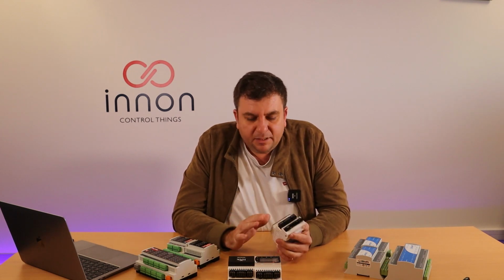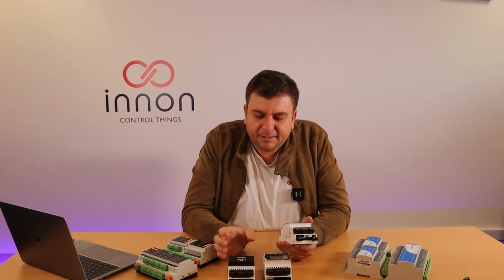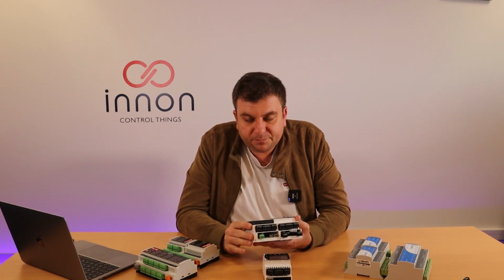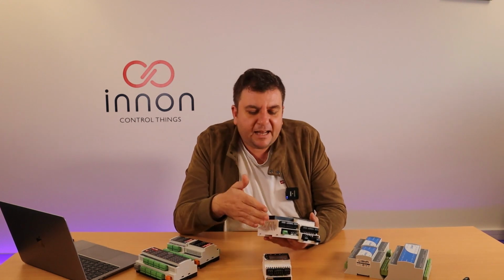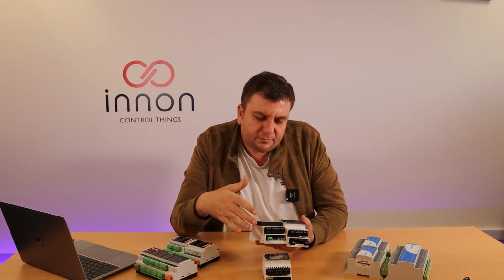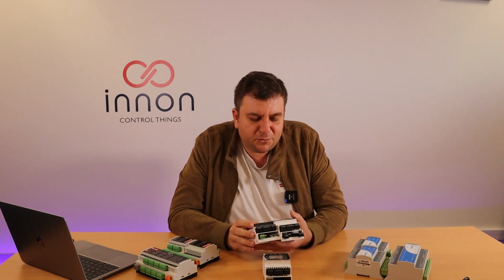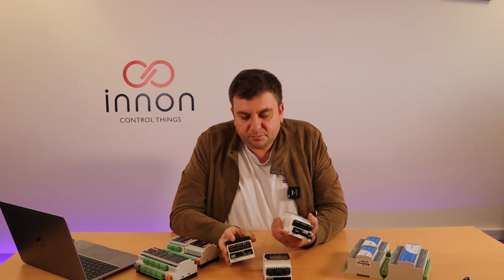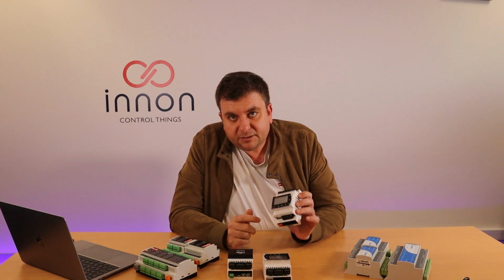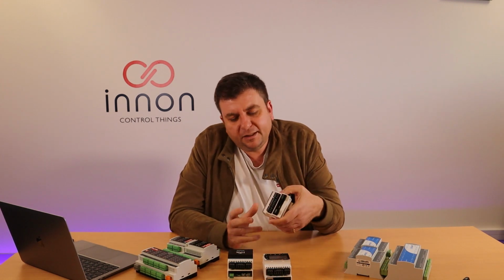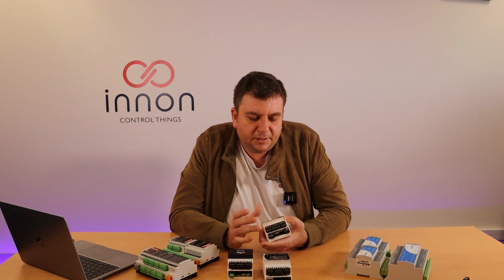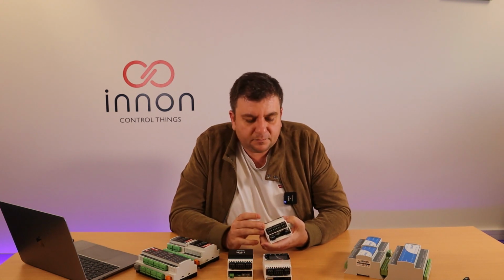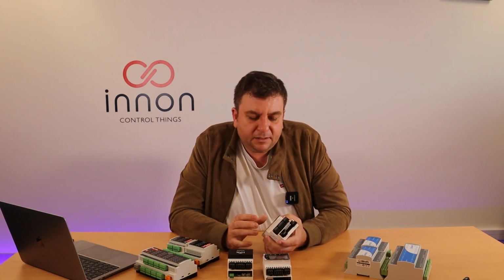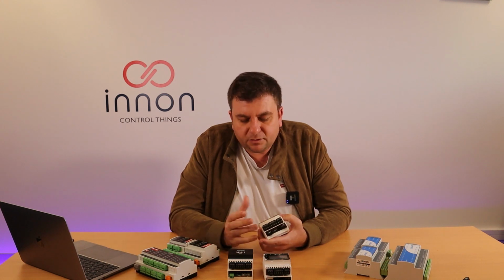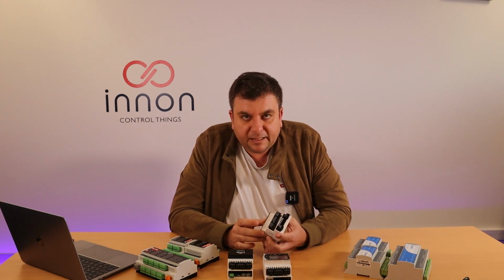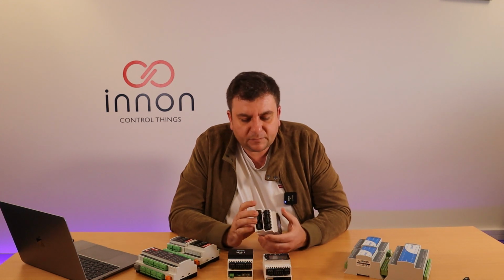Again, it's IP, we've got RS485, and we've got the expansions. A second interesting feature is you can add up to 10 of these expansions, making like a caterpillar of an I/O module, which is quite useful. Last but not least, it has a display, used for commissioning and maintenance purposes. You can override things with it, set it up, and there are built-in functions, like controlling an output based on an input in standalone mode. So those are the main features.